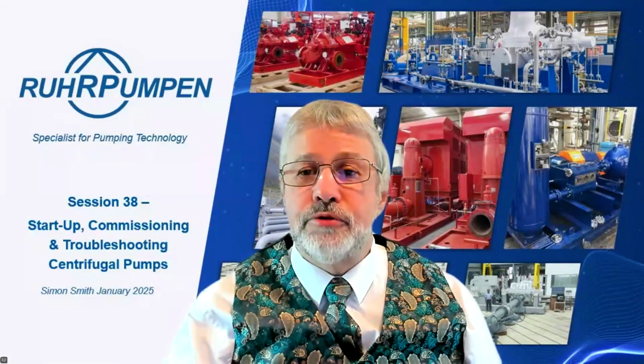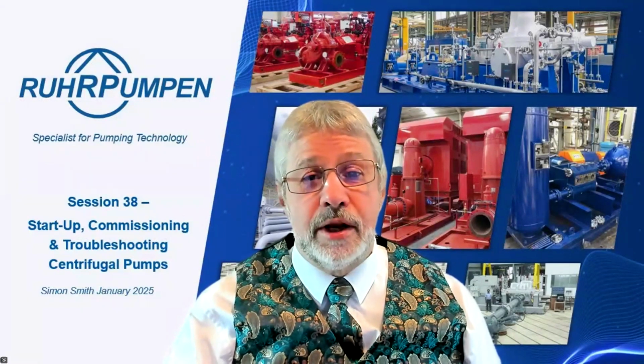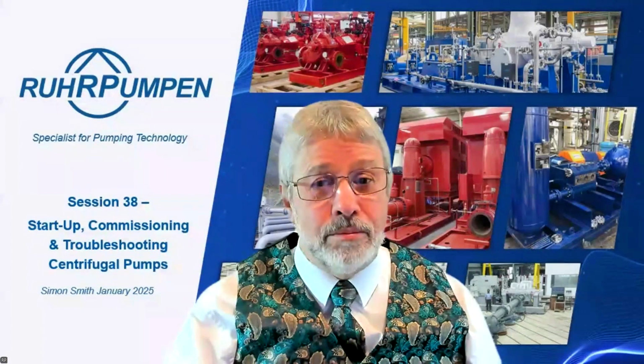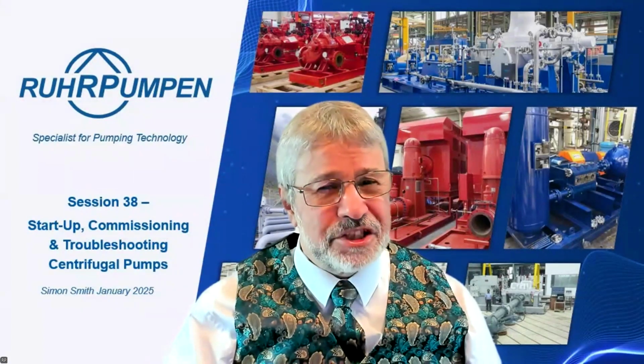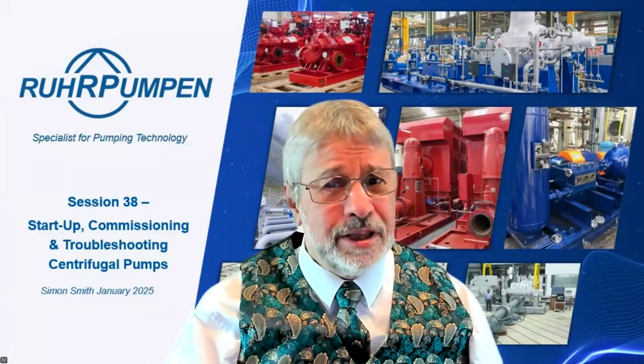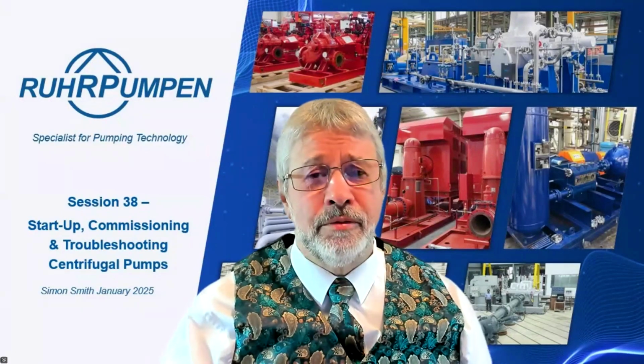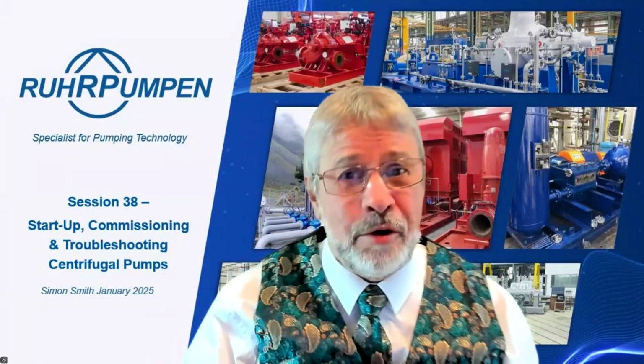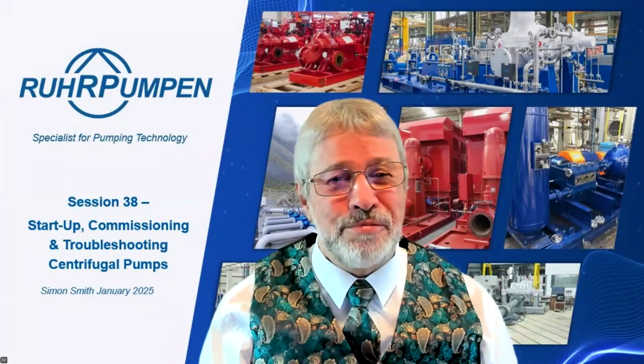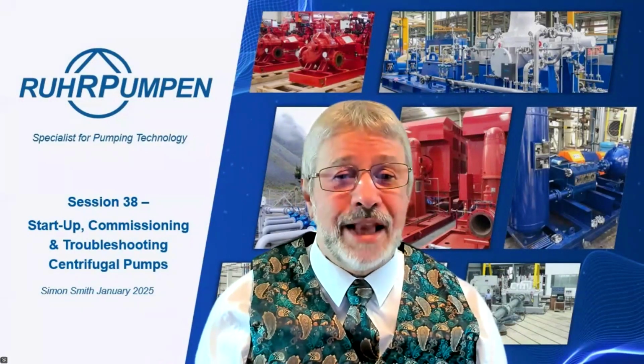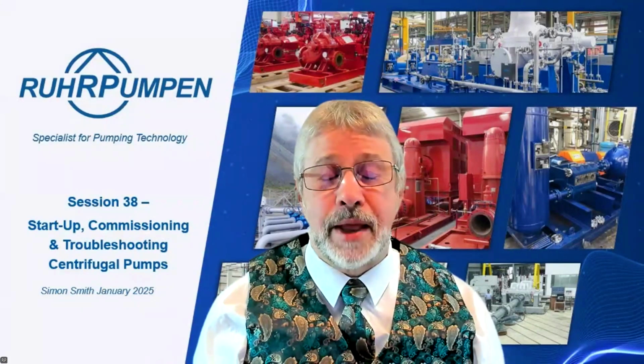Anonymous attendee, please elaborate on pump reverse rotation and its impact on pump and seal parts. Well, if the pump's running the wrong way, it won't pump properly. You won't realize it straight away because it will give some pumping. It will do some pumping, but it won't do it properly. Performance will be down to about 30% of what you'd expect.